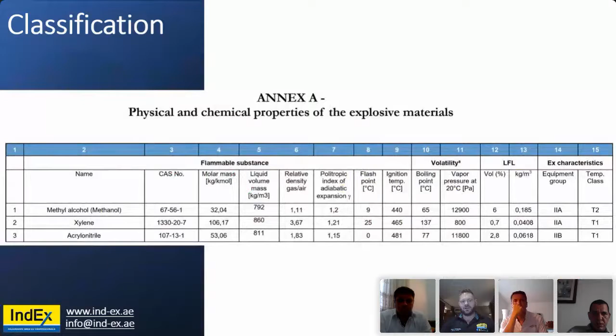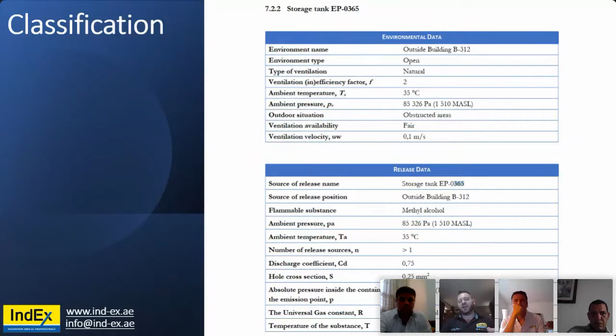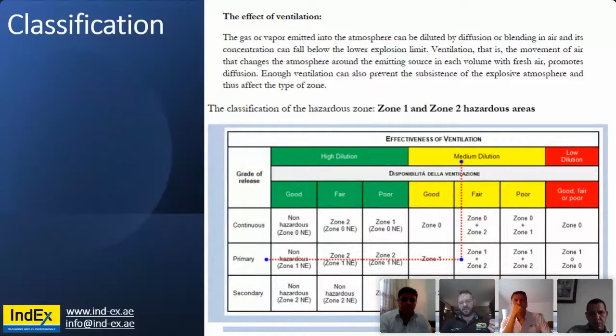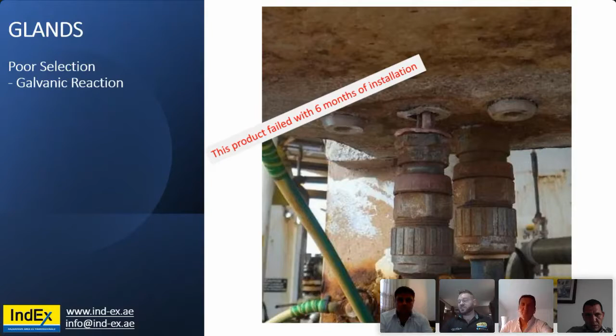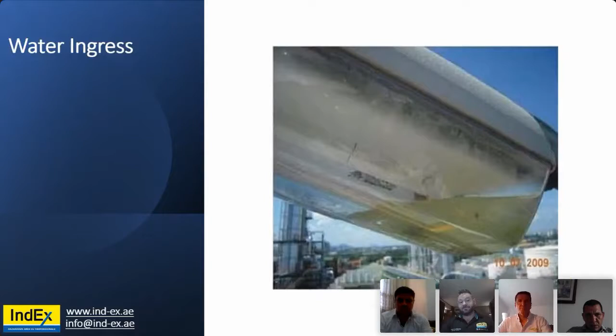Now, when we talk about hazardous area classification, once again, it's a plot plan. You define the characteristics, the source of release, you identify the environmental data, and you plot it out. It comes down to a basic risk assessment. Now, major issues that we find within industry: water in everything, poor ingress protection, failure of components, dissimilar metals, selecting incorrect products.